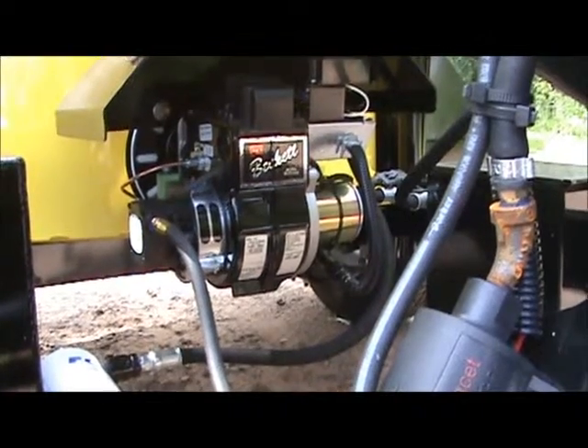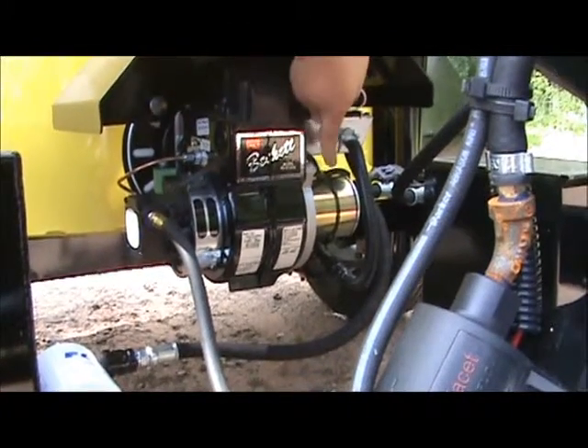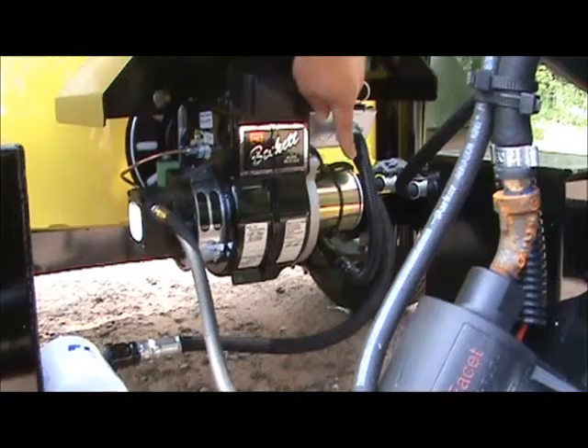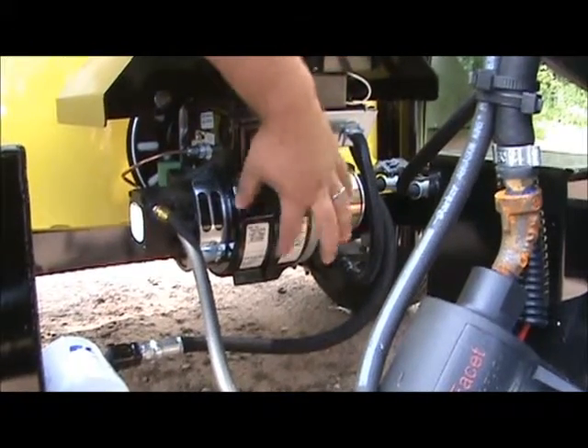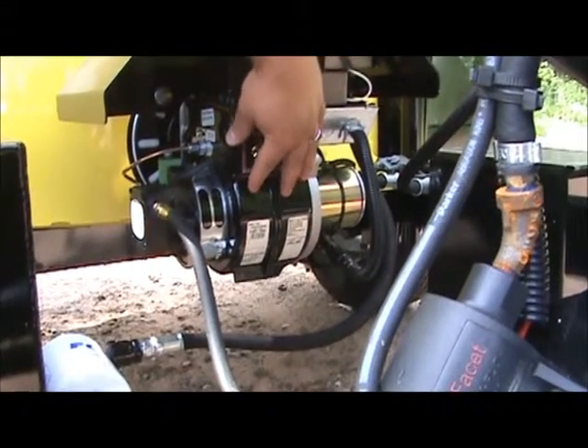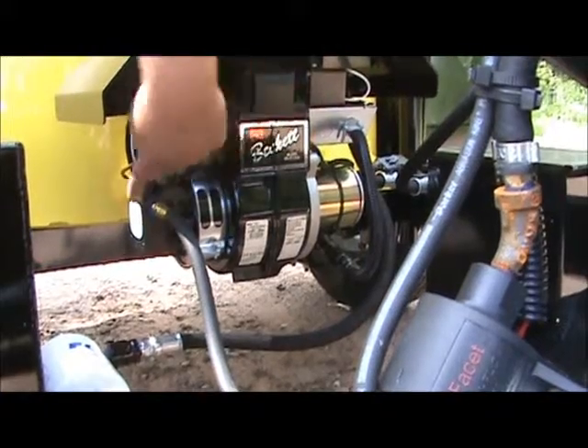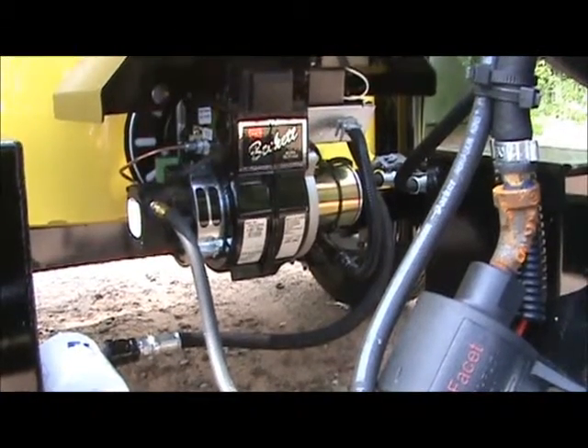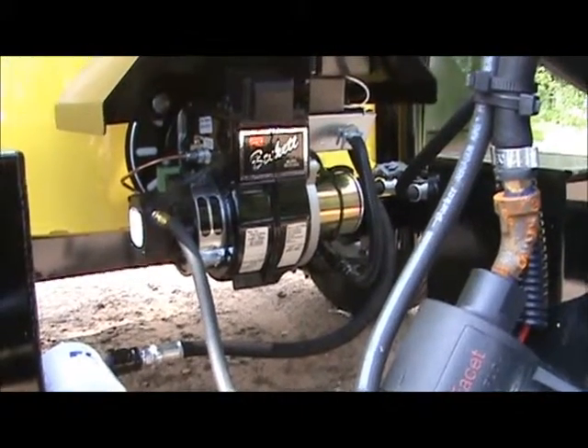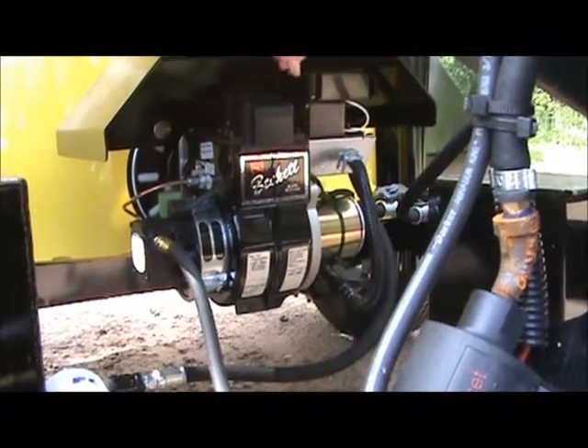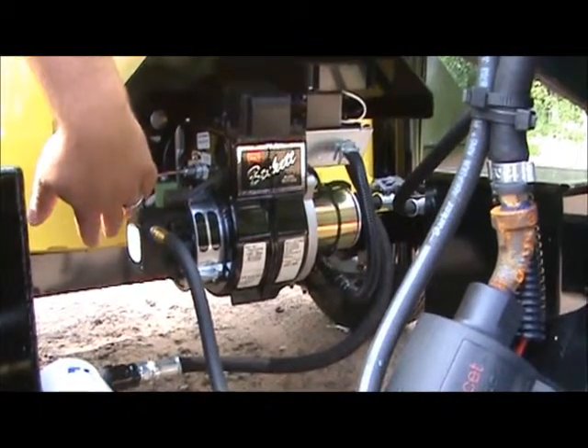The burner's made up of a handful of different components. The big shiny thing that we're seeing over here, that's actually the motor. The motor's connected to the fan. The fan's located in the main housing of the burner. And then that motor also connects to the fuel pump. So when we flip our switch on the back to turn the burner on, that motor kicks on, starts the fan, starts the fuel pump.